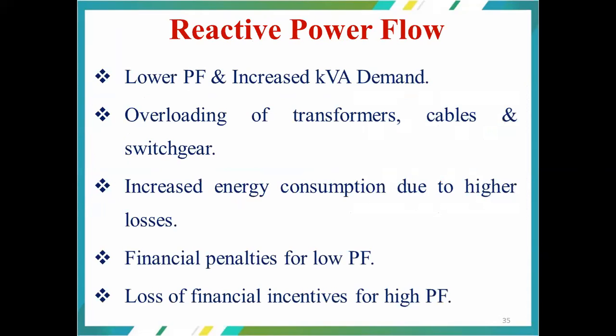that itself indicates that the loads are creating huge harmonics. And reactive power flow: whenever you are implementing or deploying any power converters, you are going to increase the kVA demand, because the kVA requirement increases due to the presence of the converting stations. This may result in overloading of the transformers, cables and switchgear, because in addition to the real power, you are going to carry the reactive power also. Increased energy consumption due to higher losses, and the magnetization current is going to increase, and you are going to have losses.